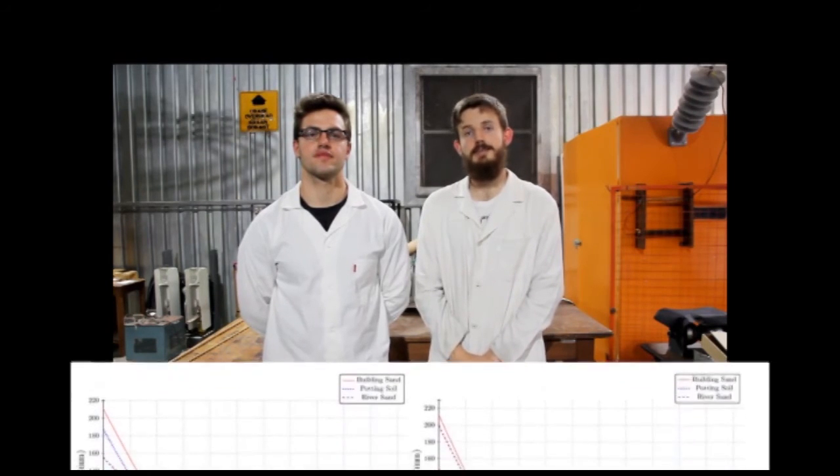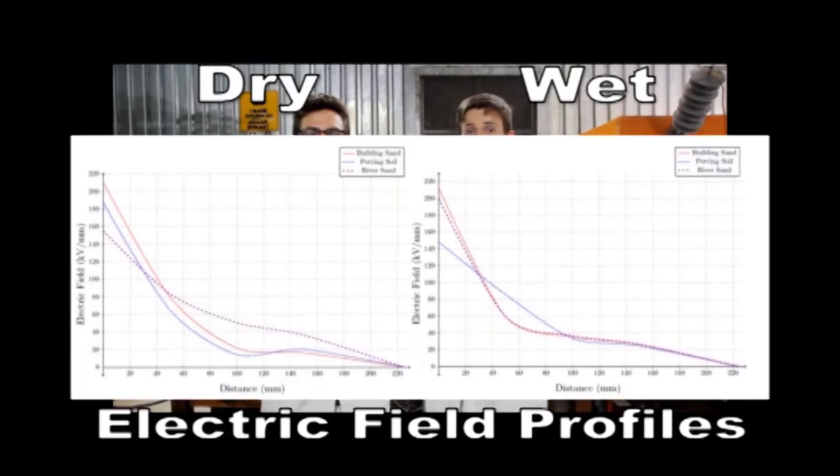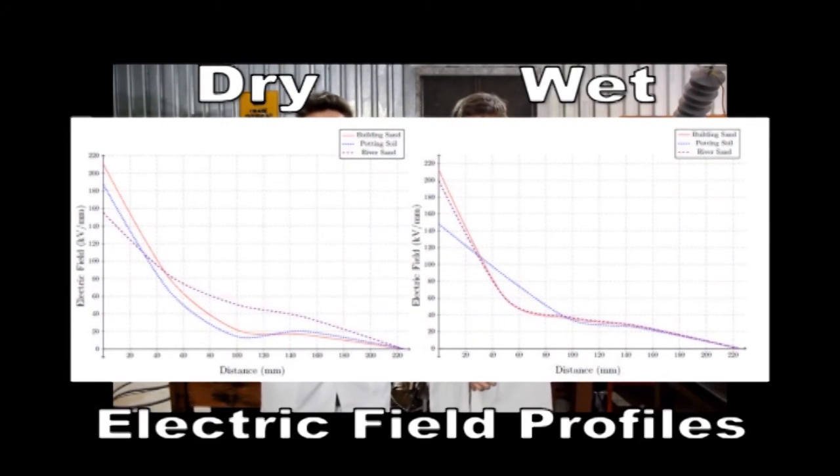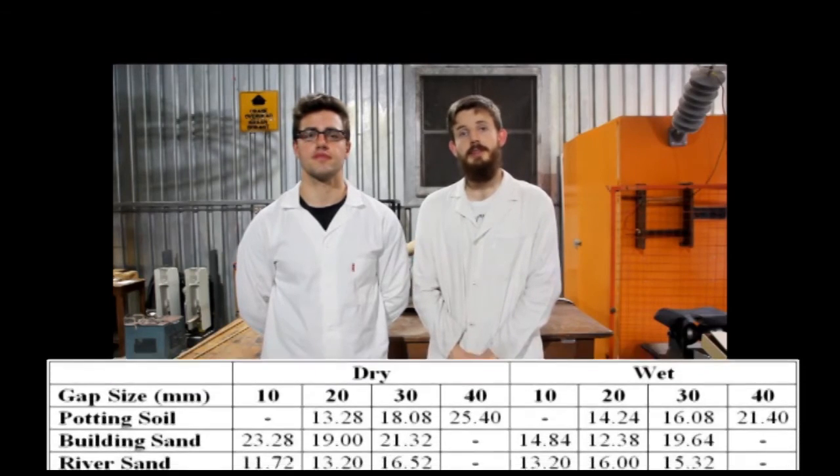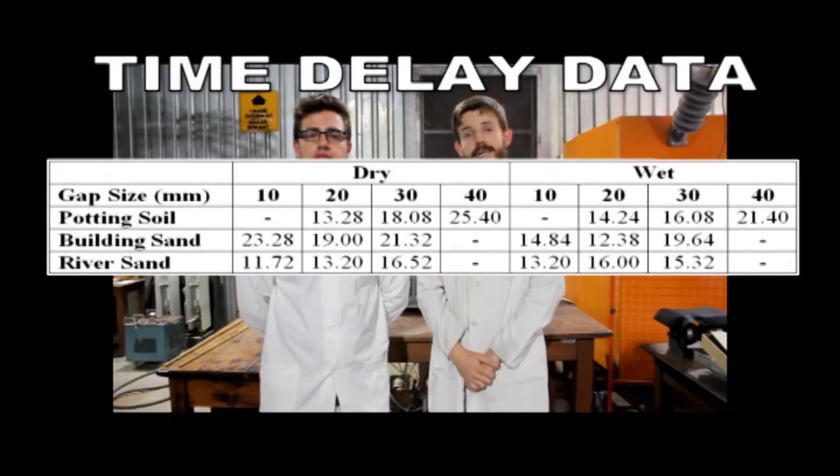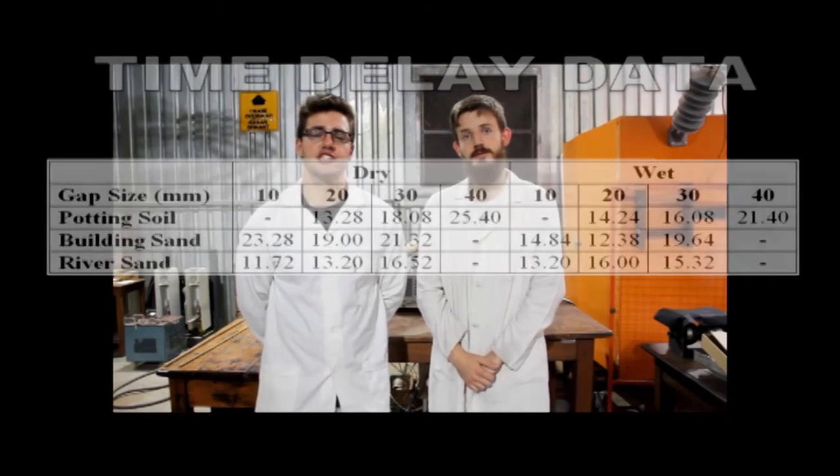In conclusion, we found that moisture content affected the electric field profiles and the ionization performances of the various soil types tested. We were also able to determine, within a reasonable degree of accuracy, the resistivity value for each of the soils tested, when compared to the values we found within literature. Time delay data gathered supported other evidence that showed that soil ionized more efficiently when wet, unless it became saturated.